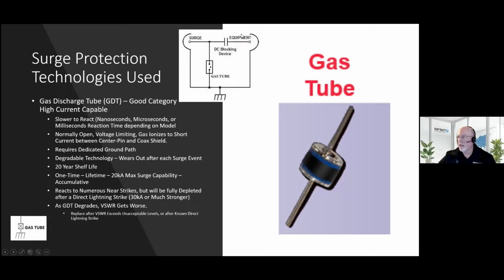This schematic is for an RF surge arrestor. And in this case, the surge will be shunted to the body of the surge arrestor, which will require a dedicated ground path to carry that surge current right to ground. Lightning wants the least path of resistance. And so you want that ground wire to be as straight and short as possible. Any bends add impedance, and then the surge will want to go somewhere else, like through your radio.